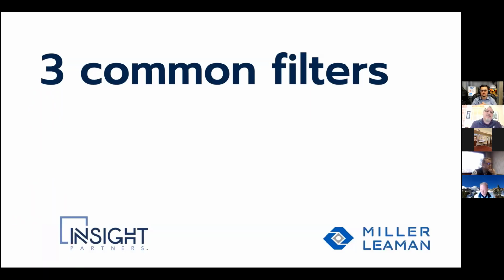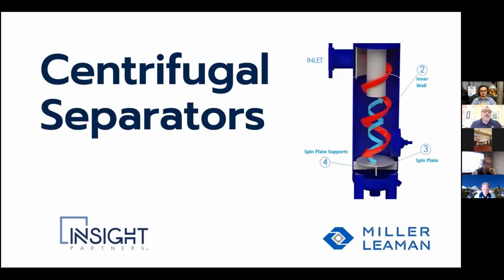Next slide. 3 common filters. There's many filters out there, but these are the 3 common ones you see as side stream or slipstream on cooling towers. I would categorize them as kind of good, better, and best. So on to the next one, you'll see a centrifugal separator. Centrifugal separation is good, and it was initially designed for the mining industry because it takes out high specific gravity particles of 2.2 or larger. So that's kind of sand, dirt, anything like that.